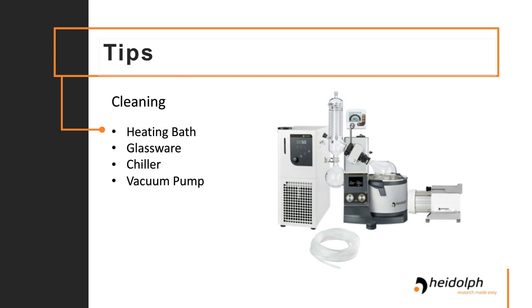Maintaining your chiller is important. The methods differ depending on what you're running through there. If you're using the manufacturer liquid, such as Cryo30, it comes with products in there that prevent algae from building up, so you might only need to replace your liquid every year or so. If you're using a home brew of water and glycol, I'd recommend replacing it more frequently, maybe every 6 months or earlier, because you run the risk of algae building up in there, and that can really screw with your system.